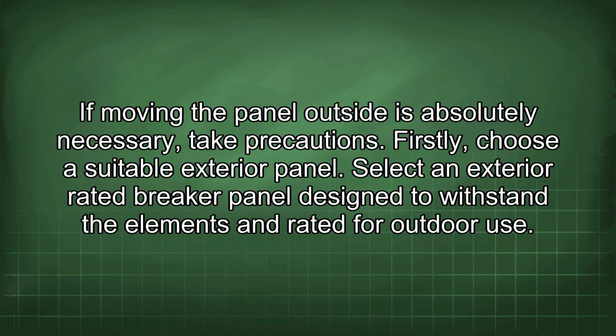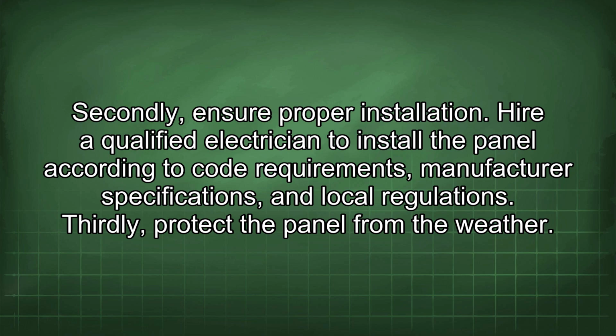If moving the panel outside is absolutely necessary, take precautions. Firstly, choose a suitable exterior panel. Select an exterior rated breaker panel designed to withstand the elements and rated for outdoor use. Secondly, ensure proper installation. Hire a qualified electrician to install the panel according to code requirements, manufacturer specifications, and local regulations. Thirdly, protect the panel from the weather.